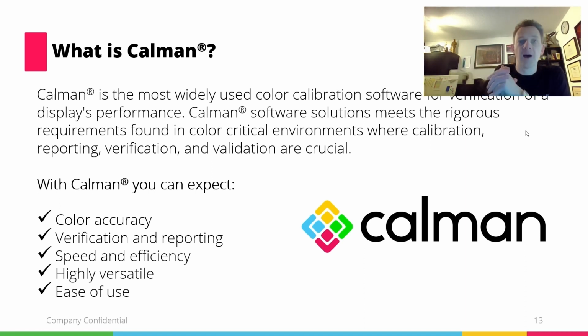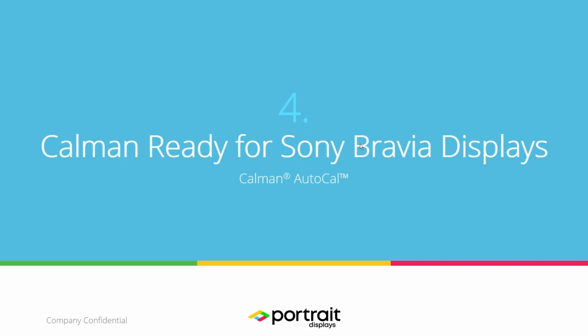The reason for that is pretty evident. It's made for verification of display performance, right? And it's made to meet the rigorous requirements found in color critical environments, where calibration, verification, reporting, and validation are important. You really want to know what you're doing. And most importantly, it allows auto calibration, calibrating displays automatically by the use of AutoCal. That's something that's part of Calman Ready, and that's the reason why we actually talk about this, right?